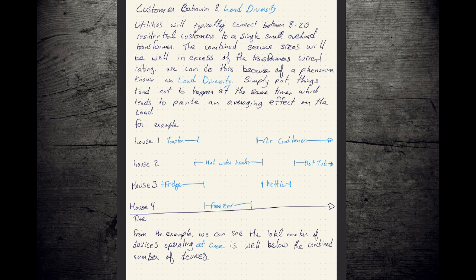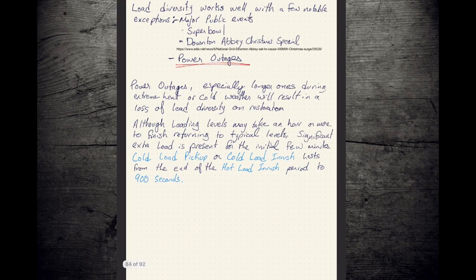What we see is an averaging effect. So if you have 5 houses, at the first house, it's the morning, someone gets up, they turn on the shower, their hot water heater comes on. Someone else is just getting out of the shower, the hot water heater turns off. Somebody starts making breakfast, they flip on the toaster, someone else is leaving for work, so they shut off the TV and all the lights, and you get all this averaging effect where things are coming on, but other things are turning off, right? The toaster's kicking off just as someone else is turning their kettle on. You get this smoothing effect that happens. And so you don't see these super high peaks that you might expect if all you were doing is looking at how much equipment was connected. So load diversity works really well.